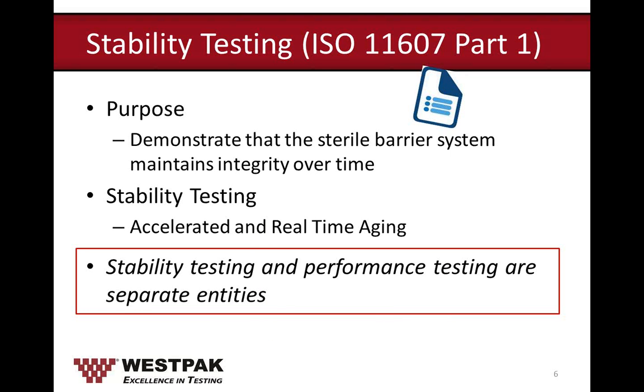ISO 11607 is a guidance document with two parts; our main focus is Part 1. Stability testing shall be performed using real-time aging. However, since real-time aging takes a while, it is acceptable that accelerated aging is considered sufficient evidence to claim expiration dates until the data from real-time aging studies are available. Real-time aging and accelerated aging tests should begin simultaneously.